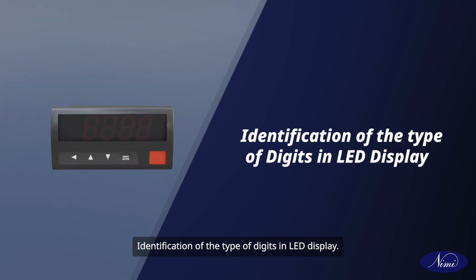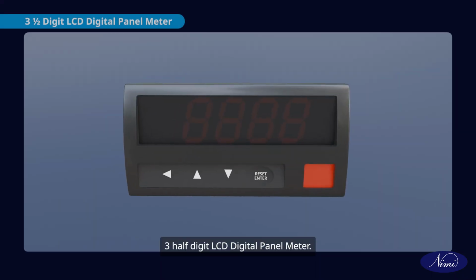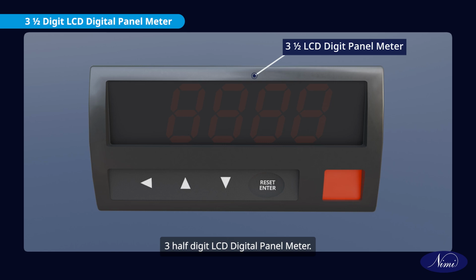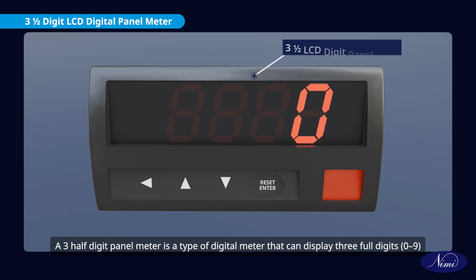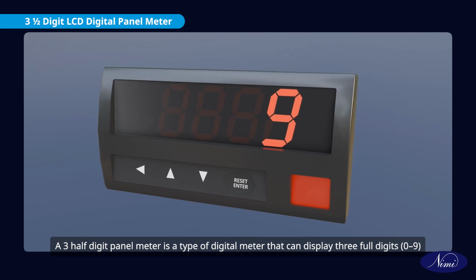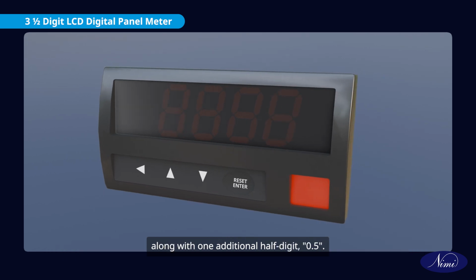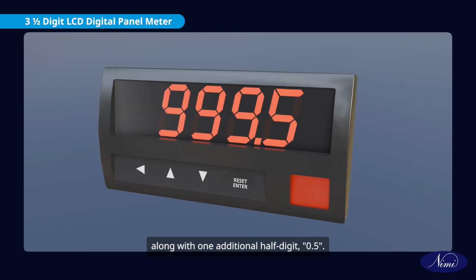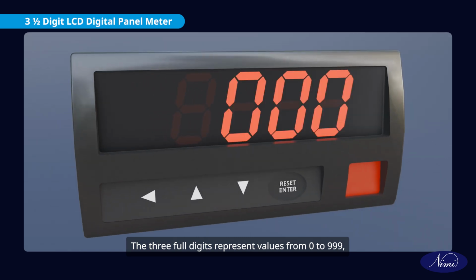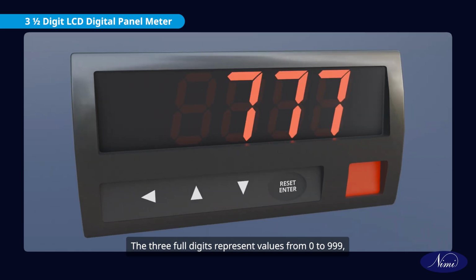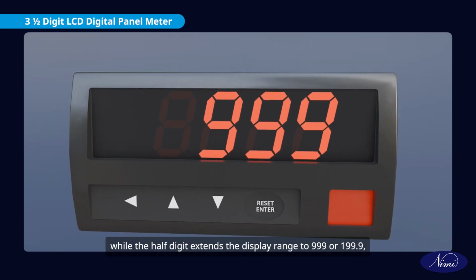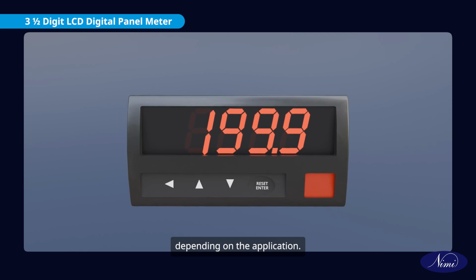Identification of the type of digits in LED display. 3 half-digit LCD digital panel meter. A 3 half-digit panel meter is a type of digital meter that can display 3 full digits 0 to 9 along with one additional half-digit 0.5. The 3 full digits represent values from 0 to 999 while the half-digit extends the display range to 1999 or 199.9 depending on the application.